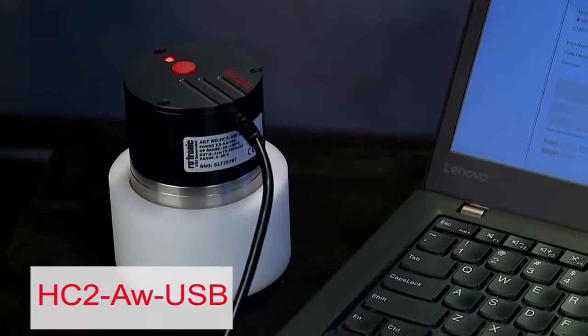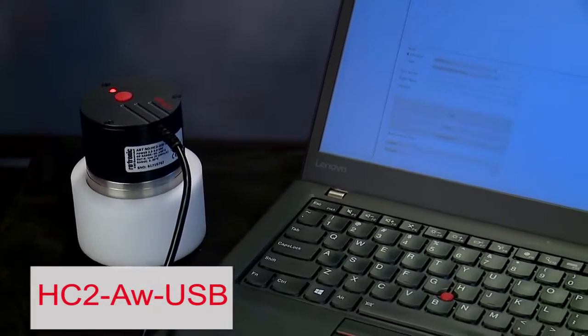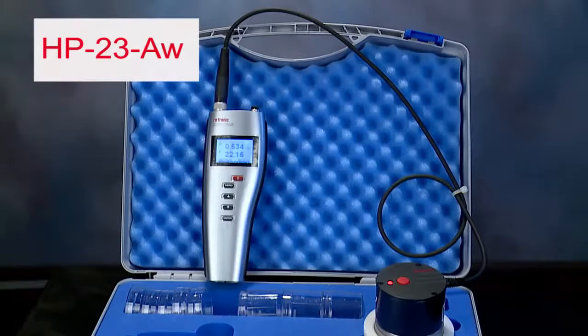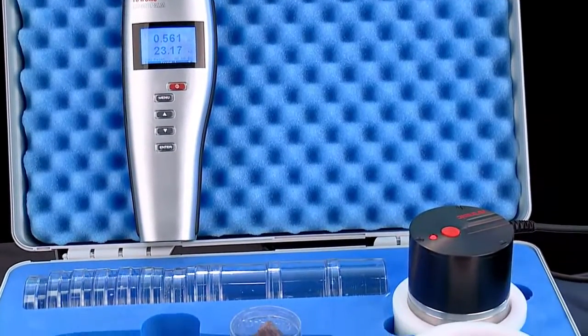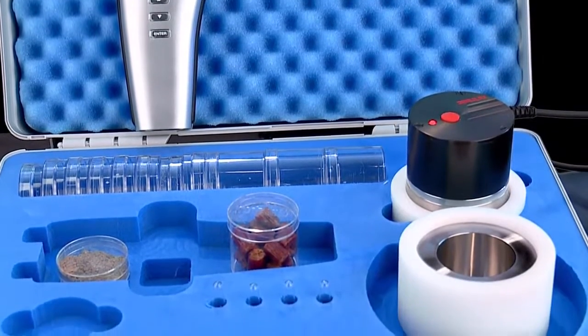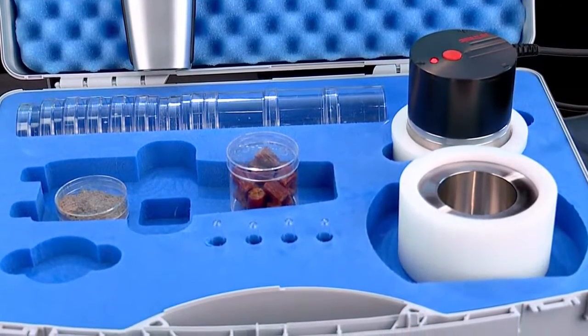In our first two videos on water activity measurement, I reviewed Rotronic's line of AW instrumentation and demonstrated the ease of testing using the HC2 AW USB probe with Rotronic's HW4 software and the use of the HP23 AW set. Today, I'm going to go into more detail on how to calibrate the popular HP23 AW portable water activity instrument set. The set consists of three main components: the HP23 AW handheld, the HC2 AW measuring probe, and the stainless steel sample holder. I would like to first review a few points regarding calibration and adjustment of the instrument.